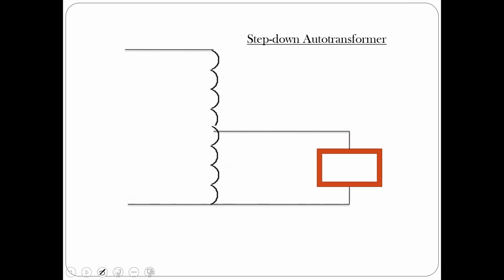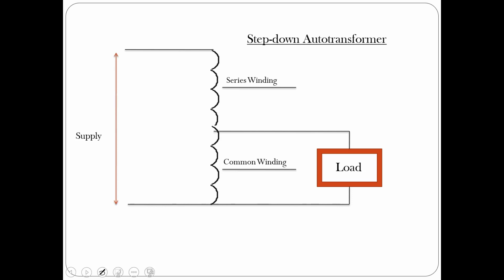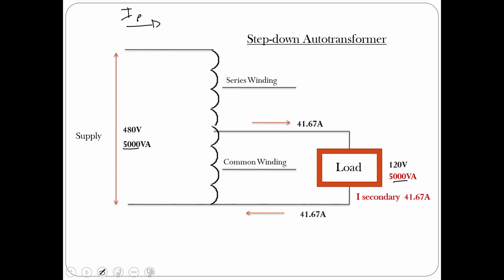Let's have a look at a step-down transformer. So in this scenario, we've got our supply and our load, and this time we'll identify our windings. Our series winding on our step-down transformer is in series with the source or the supply. And the common winding, well, its voltage is the same voltage the load sees, so it's common to the load this time. All right, so our supply is 480 volts. Looks like our load is 5000 VA. All right, so we're going to do exactly what we did last time. We're going to determine the current in each wire. So if I have a 5000 VA load, VA output is the same as VA input. So the current of the secondary, we take 5000 divided by 120, it's 41.67 amps.